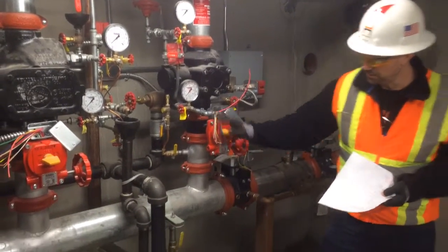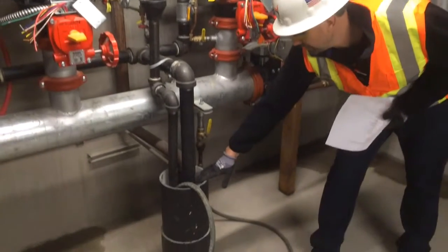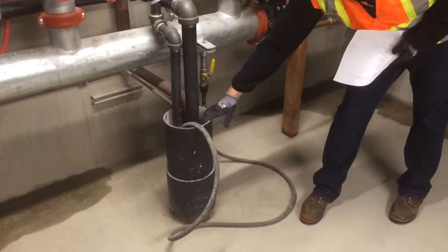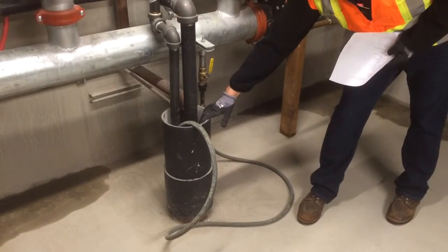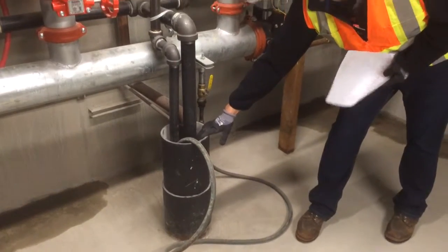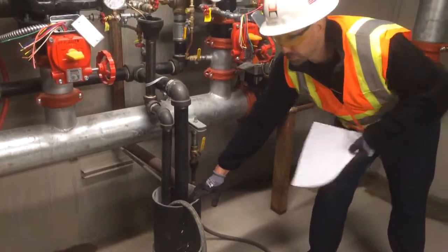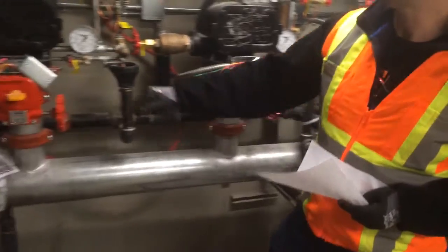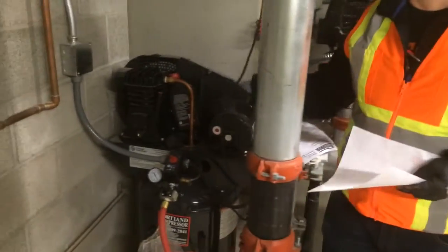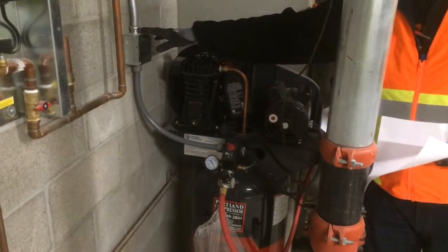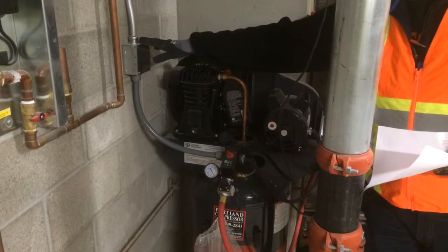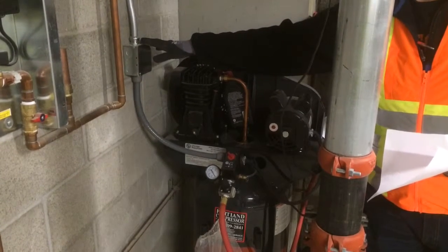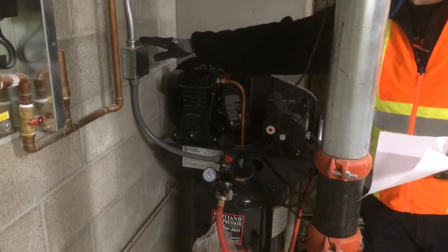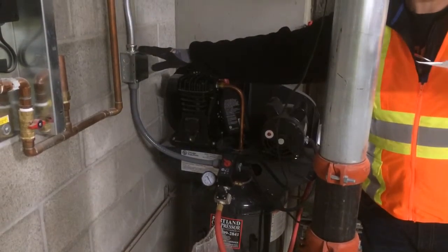Plumbing coordination. This drain is very important. It needs to be at least a minimum 8 inches in size. Sometimes you'll see this drain as a mop sink, and that never works. It'll flood the basement. Electrical coordination with the compressor. These compressors need to have a dedicated circuit, hardwired. Many times you'll see an outlet, and that's not acceptable. You'll need to redo that and have a dedicated hardwired circuit.